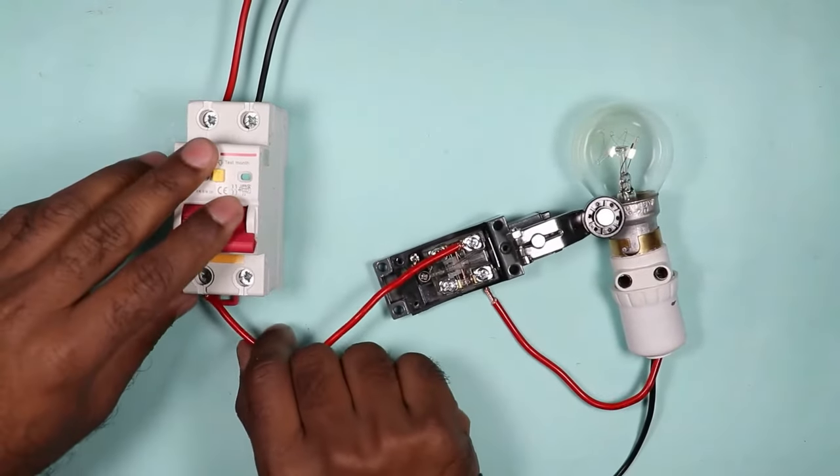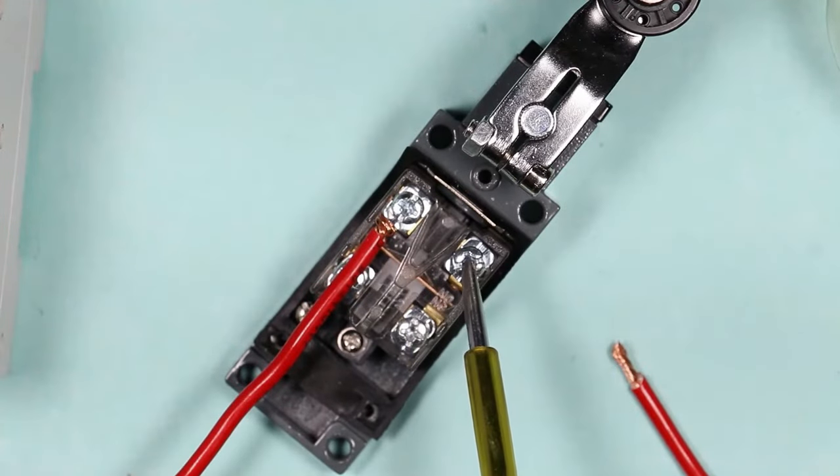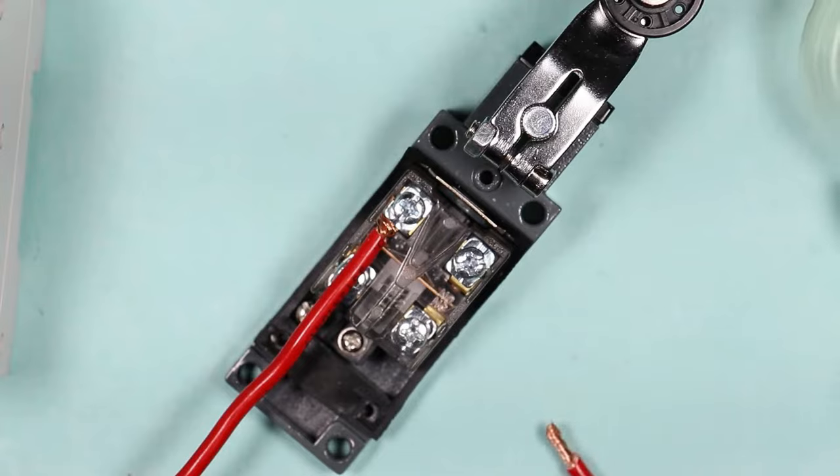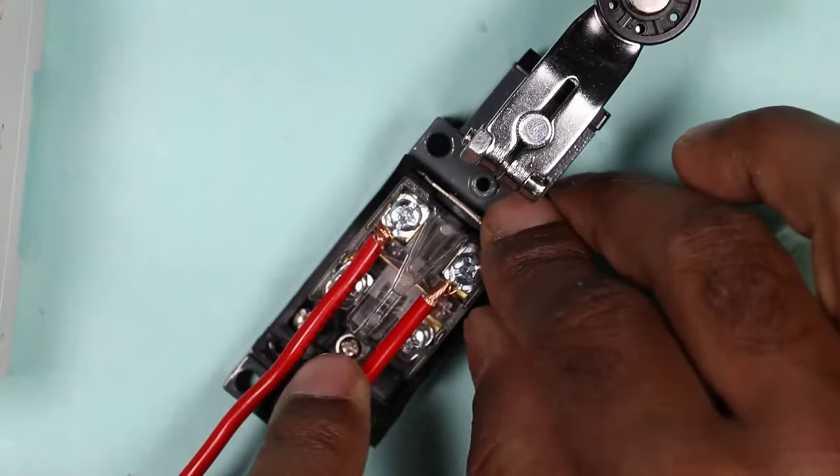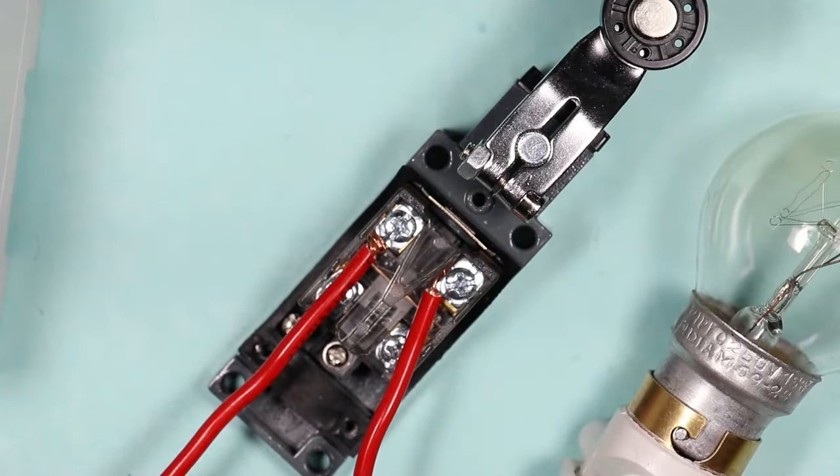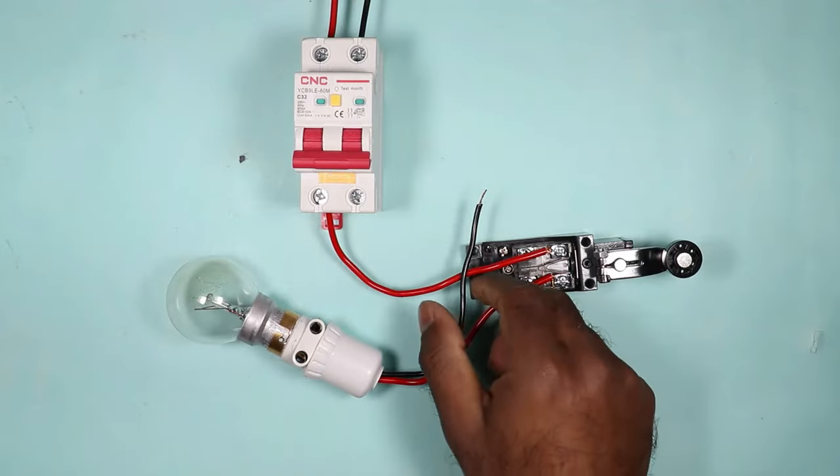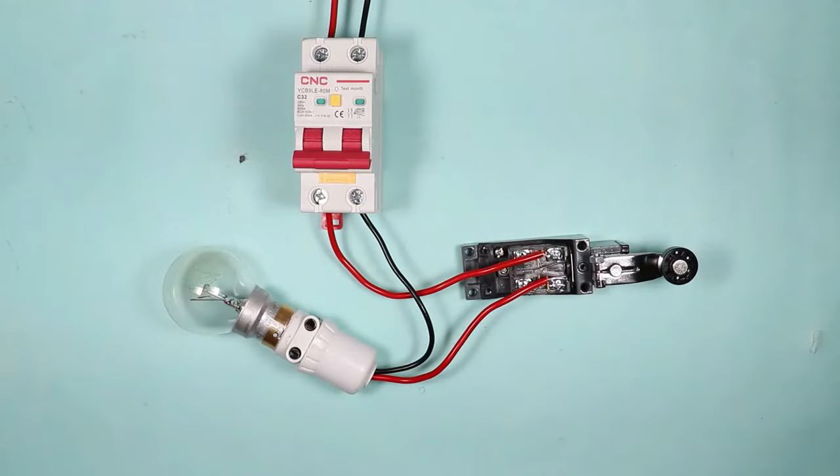For now, I am explaining connection with NO contact. Later, I will explain with NC contact. We will receive output of this NO contact at this point. So I will connect this phase wire of lamp to this point. This means phase supply will reach to lamp. We also need to provide neutral power supply to this lamp. So I will directly connect this neutral wire with neutral point of MCB.